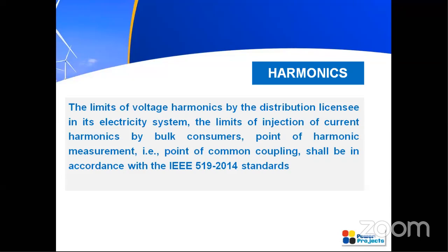But once you are integrating your wind farms with the grid, the voltage harmonics and current harmonics limits have to be checked. The limits of voltage harmonics and current harmonics have to be checked with reference to the standard IEEE 519 2014. Some may be aware of the standard and some may not have an idea, so I will show you the voltage limits prescribed in this standard. Our Indian grid code requirements say that with respect to this standard, IEEE 519 2014, we have to check our voltage distortion limits and current distortion limits.